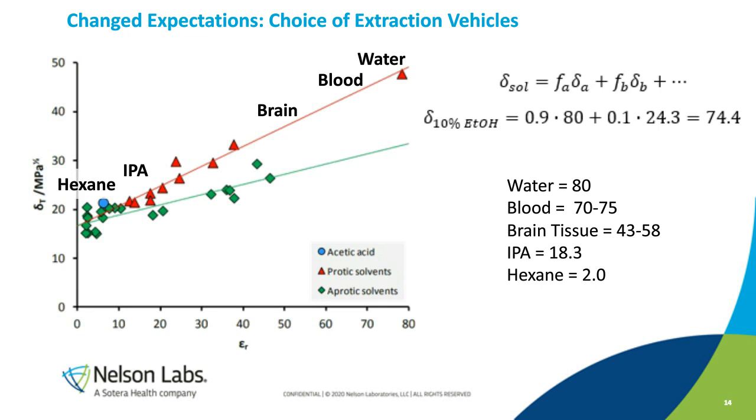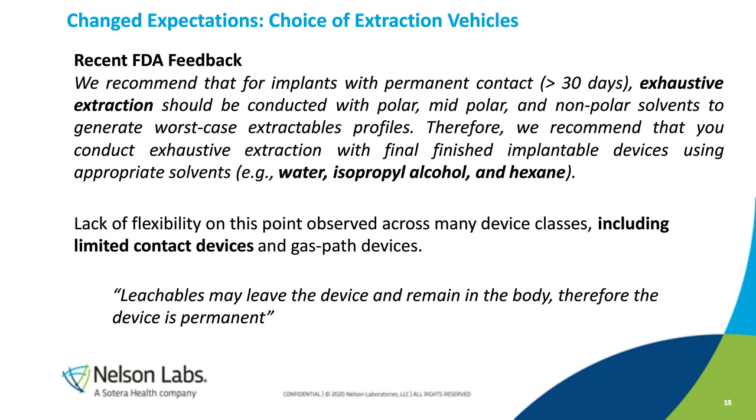Of course, we understand that the expectation from a regulatory perspective is that you really should have at least 3 solvents. It used to be 3, a polar, a midpolar, and a nonpolar, for just permanently contacting devices. I've seen the FDA really want that even for prolonged and in some cases limited contacting devices.